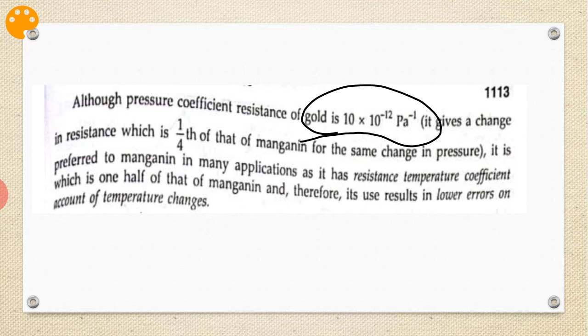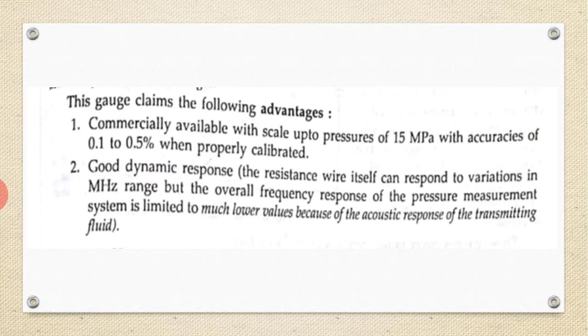The pressure coefficient of gold is 10 into 10 raised to minus 12 per pascal. It gives a change in resistance which is one-fourth of that of manganin for the same change in pressure, so gold is preferred over manganin. Some of the advantages are a scale up to 15 megapascal, accuracy of 0.1 to 0.5% when properly calibrated, and good dynamic response.